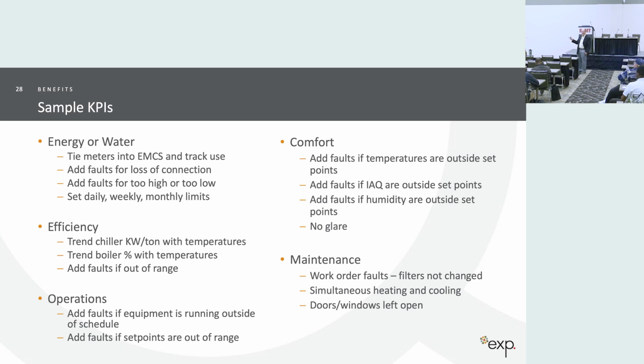You want to make sure you get clear data, because once you lose data, you lose that continuity of data, and you need that to do any analytics. You can do faults for too high or too low. So let's say you don't want to go over a peak demand, or you don't want your bill to be a surprise. You can set limits on that and have a fault. You don't necessarily want an alarm. You're not going to shut down any systems, but you want to know about it right away. You don't want to wait until the bill comes. And then setting daily, weekly, monthly limits. So this is more overall use, hourly use.